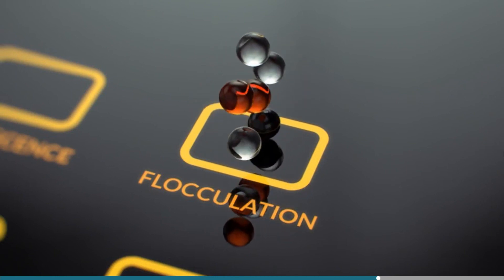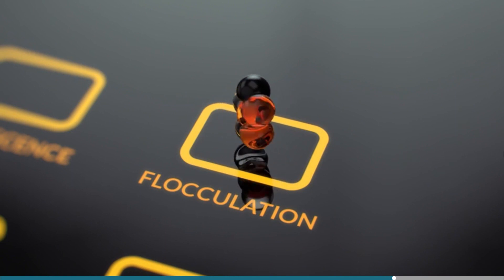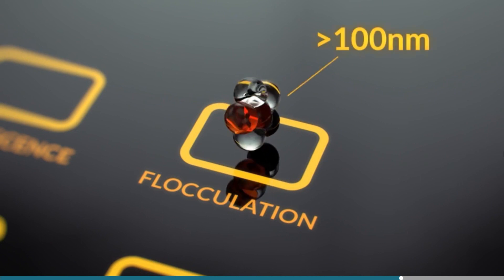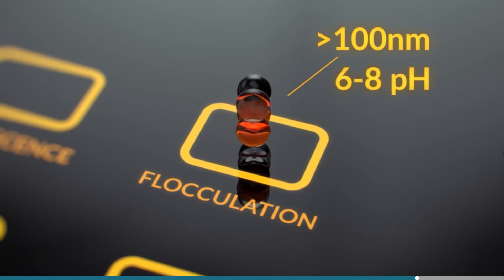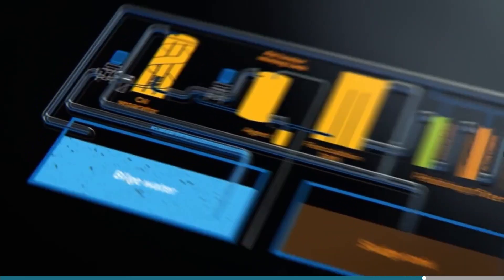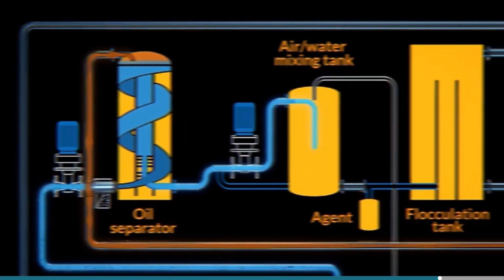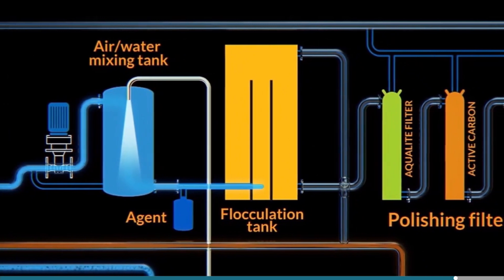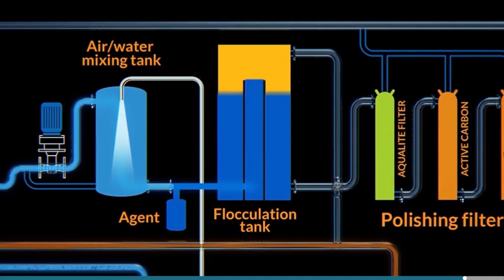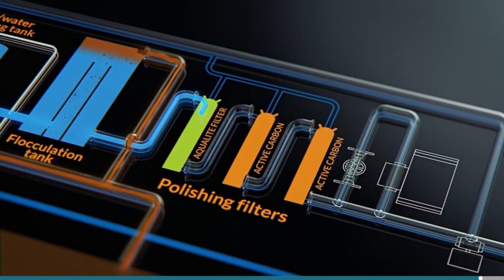Flocculation is a process by which two or more particles aggregate and stick together without losing their individual boundaries. We help the process along by adding a flocculating agent, forming particles larger than 100 nm — called flocks — which then settle. This works best at a pH of 6–8. The stages of separation are: Step 1, oil separation; Step 2, aeration; Step 3, flocculation; Step 4, processing and skimming of flocks; Step 5, filtration through three inline filters; and Step 6, overboard discharge at 0–5 ppm.